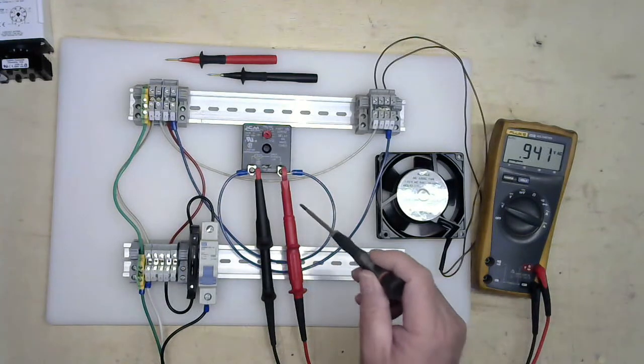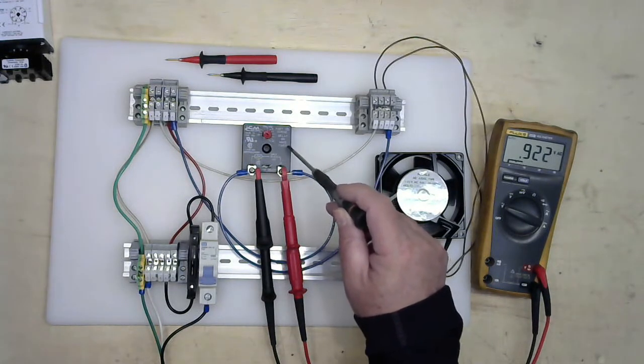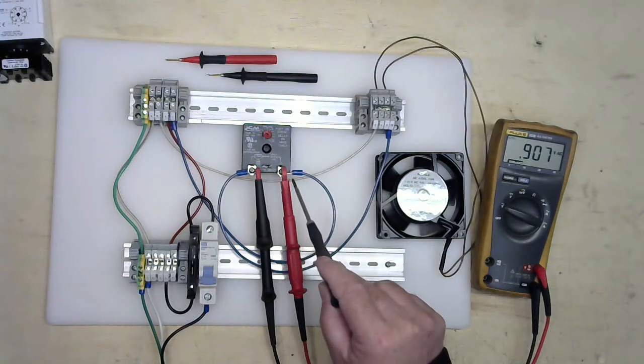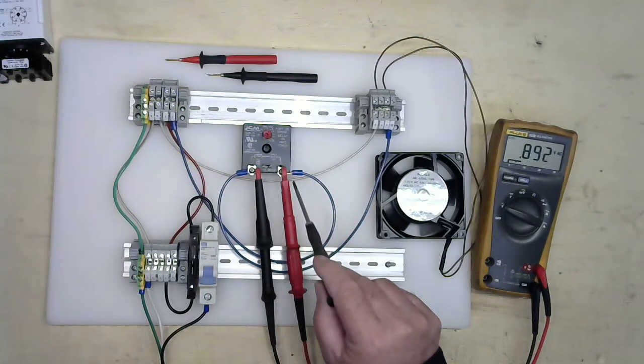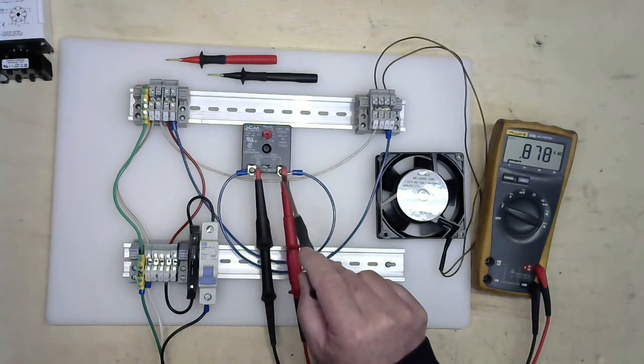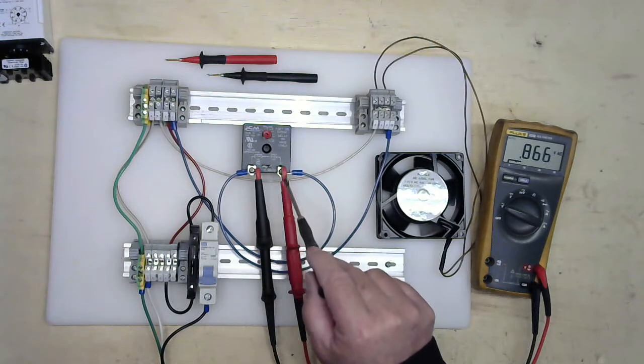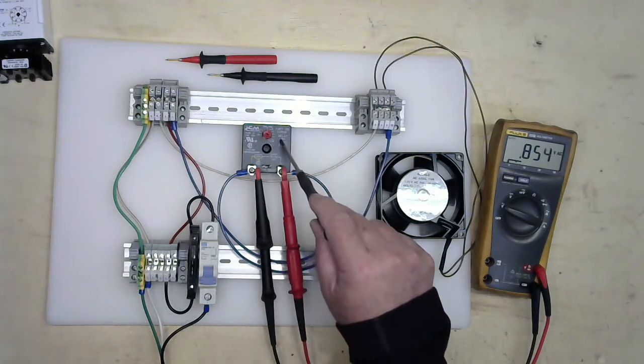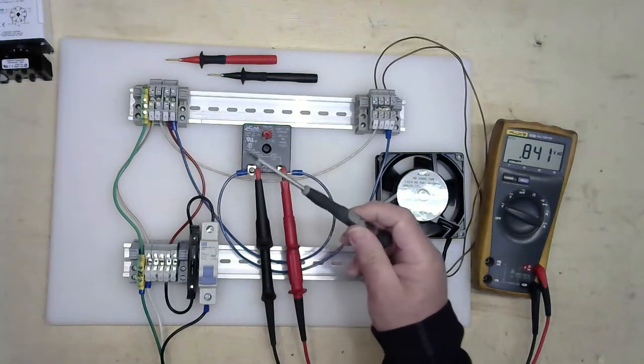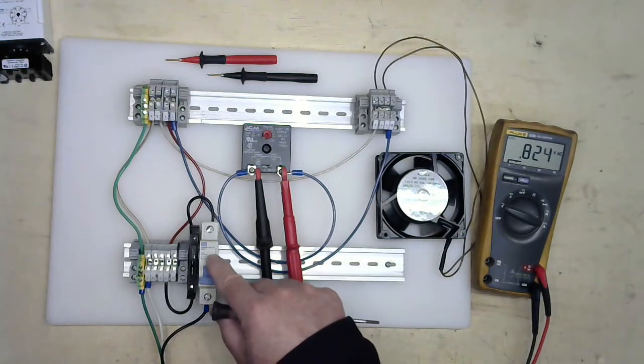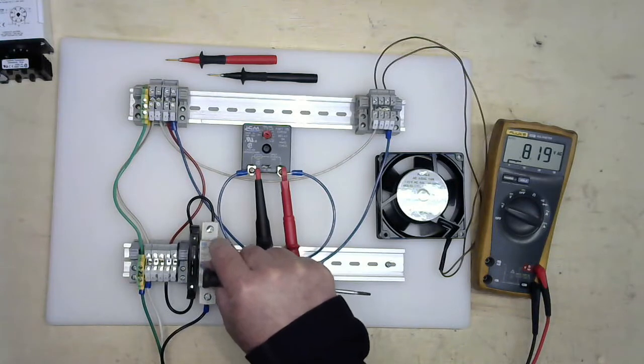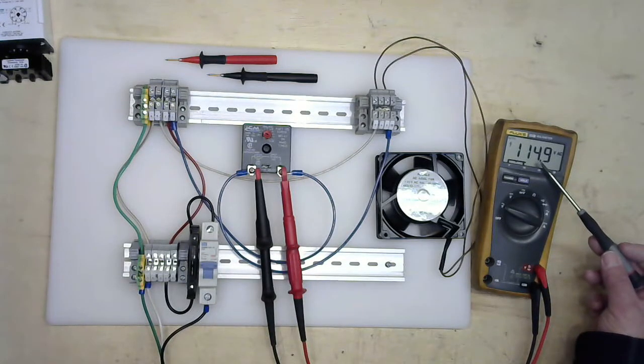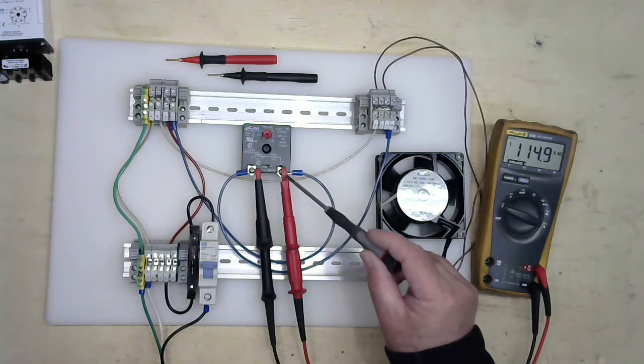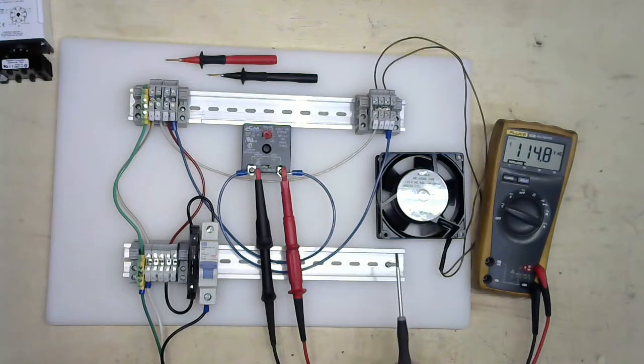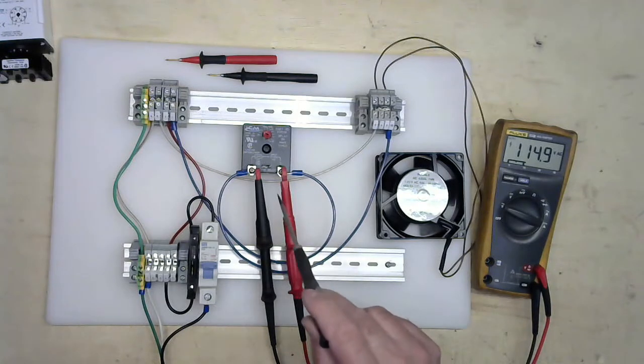Okay, now I have my single input delay on timer set. I am now checking my nominal voltage from the input to my output. This is just going to show you that once I actually receive input power, I'm going to have my same nominal voltage on my load until my contact closes, which basically signals an open circuit versus a closed circuit. My circuit breaker is currently open. I'm going to close my circuit breaker. As you can see here, I am now getting voltage to the input of my timer. My time delay is going to start timing out, and then my motor will energize once the timer does the timing function.